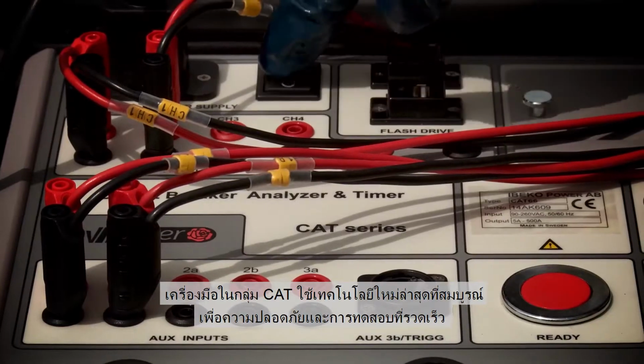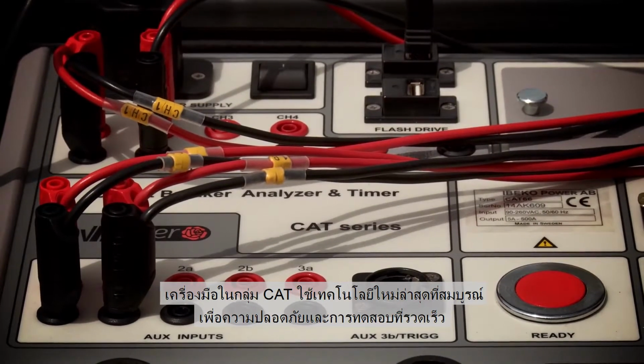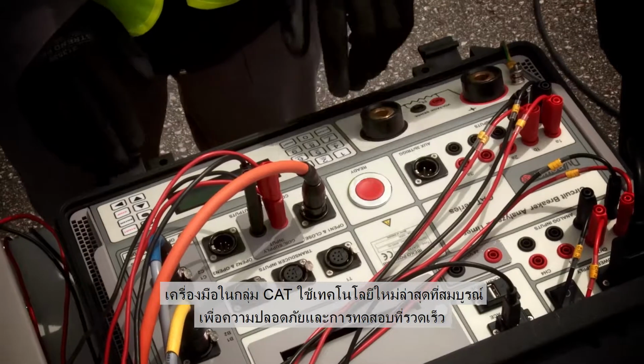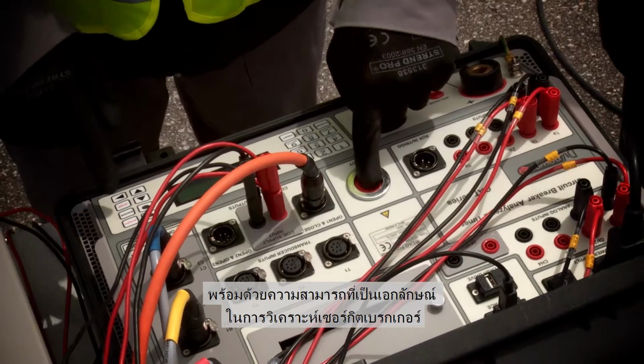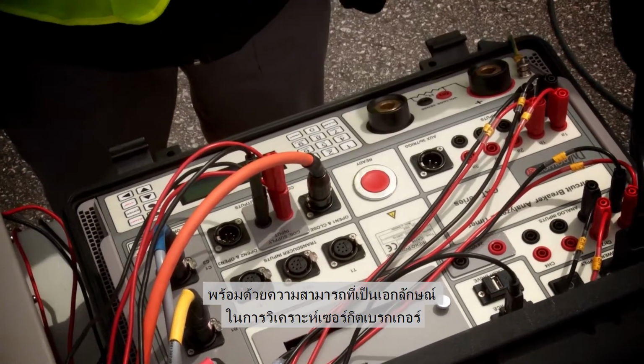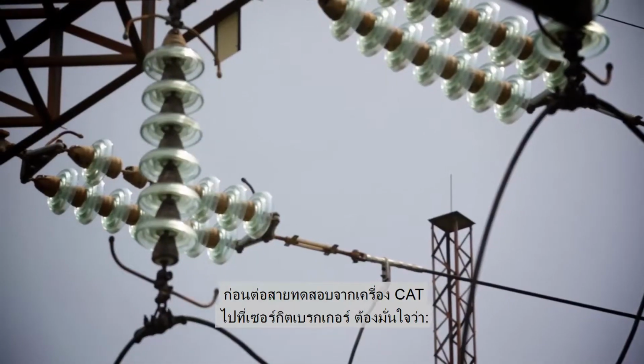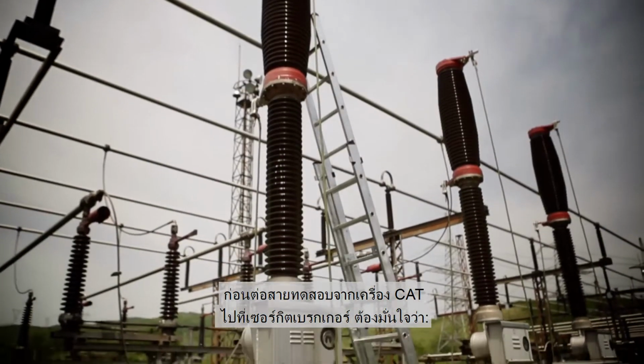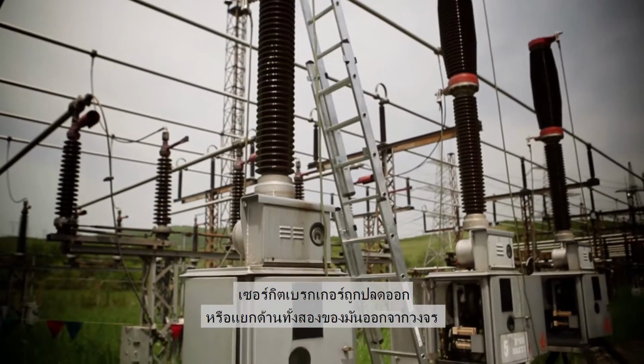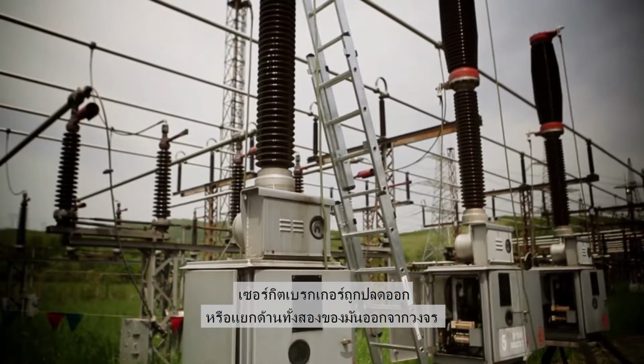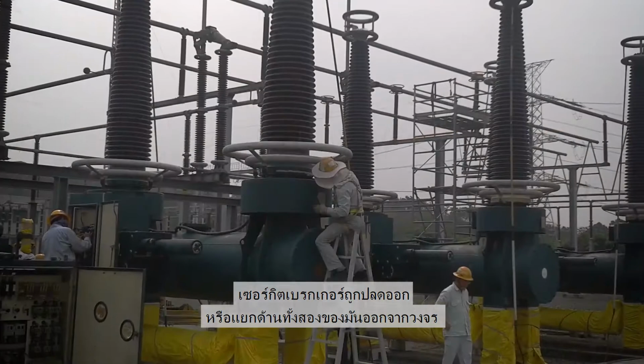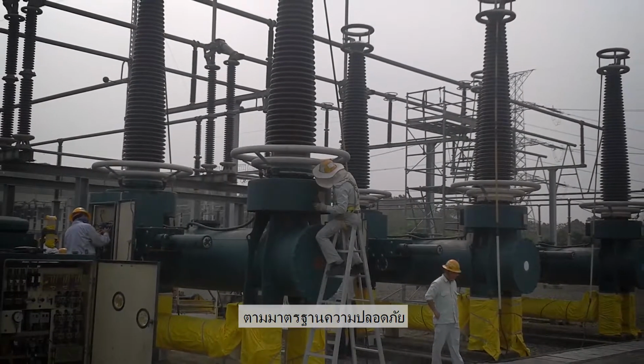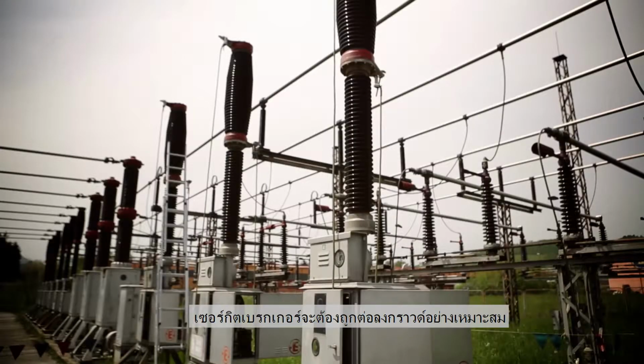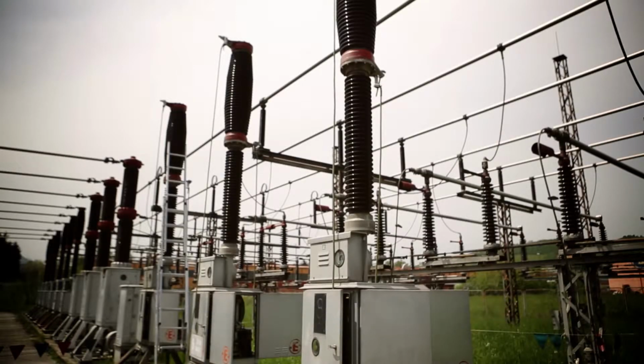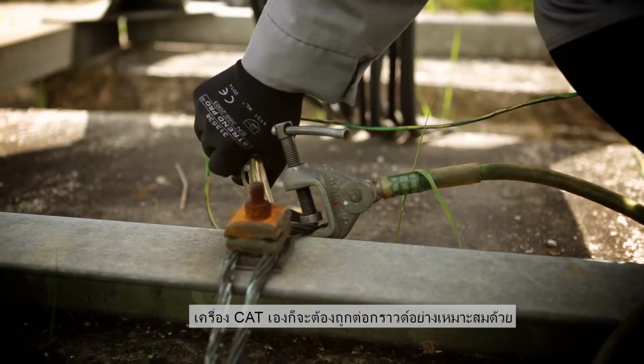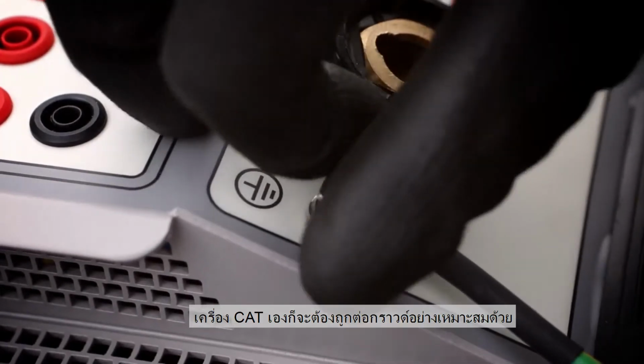The CAT series instruments utilize the latest technological achievements in safe and fast testing, with unique technical capabilities of circuit breaker diagnostics. Before connecting the CAT to a circuit breaker, make sure that the circuit breaker is disconnected or separated from its circuit on both sides of the breaker in accordance with the national safety regulations. The circuit breaker is properly grounded to a protected ground. CAT itself is properly grounded.